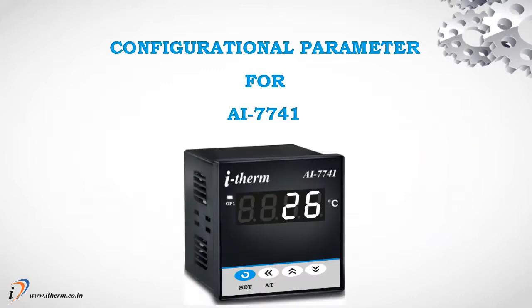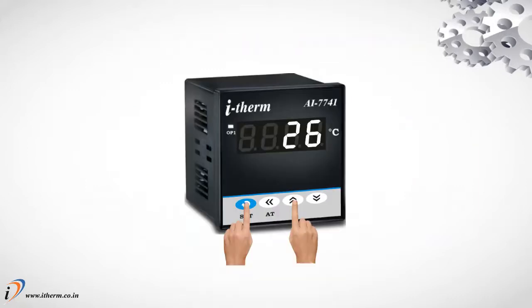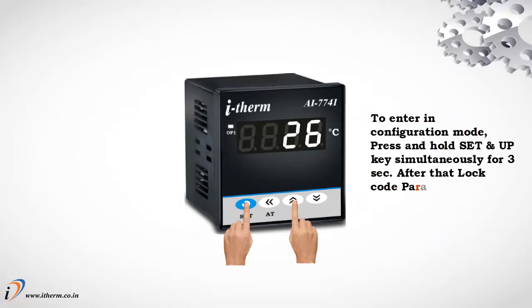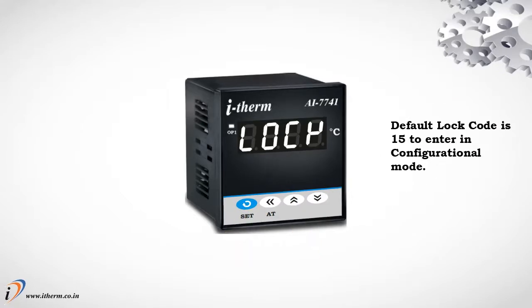Configurational parameter for AI7741. To enter in configuration mode, press and hold Set and Up key simultaneously for 3 seconds. After that, lock code will appear. Default lock code is 15 to enter in configurational mode.